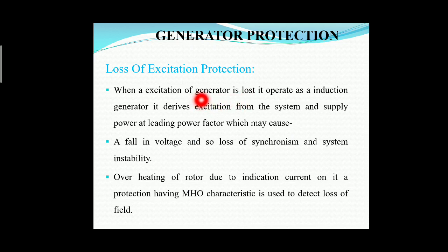When the excitation of the generator is lost, it operates as an induction generator. It draws the excitation from the system and supplies power at a leading power factor.